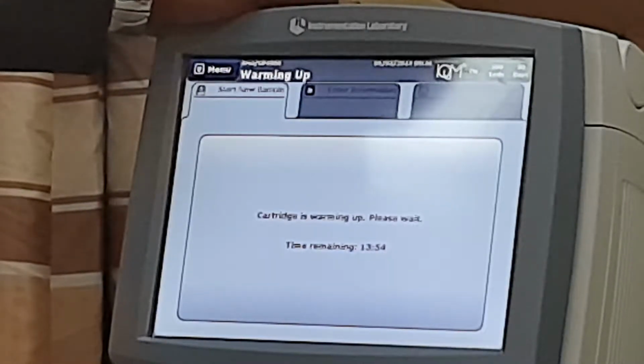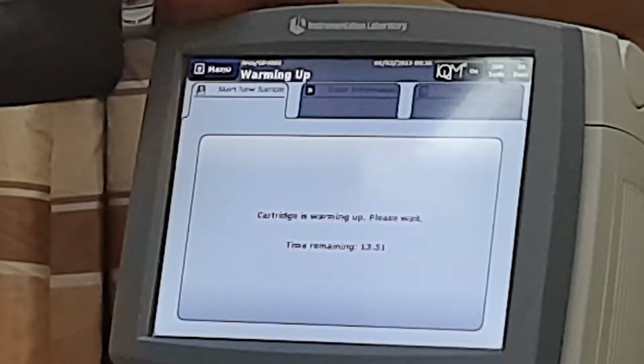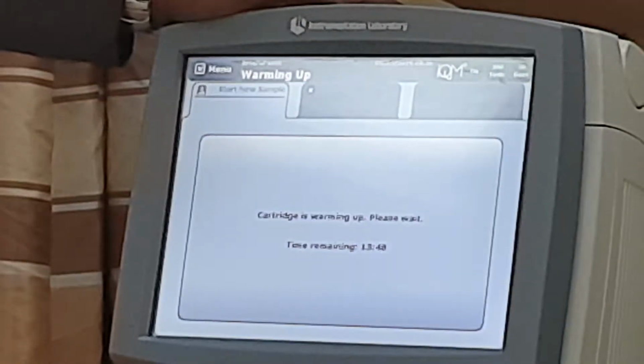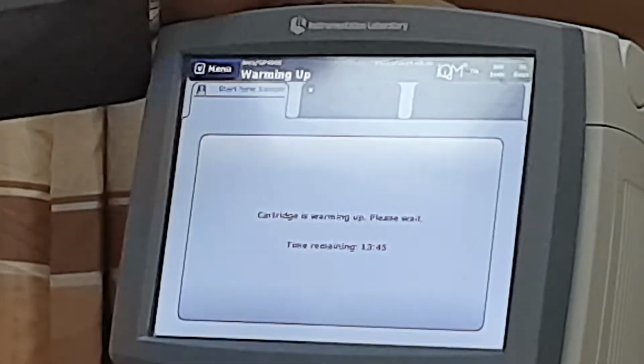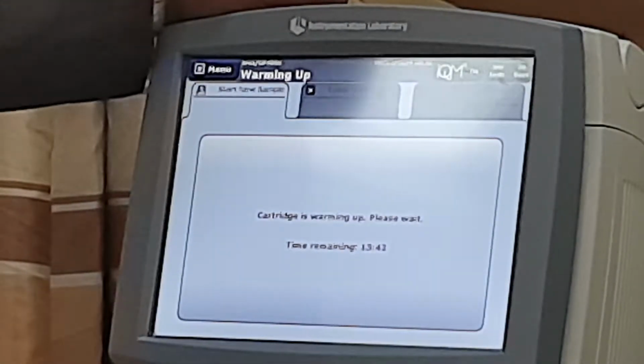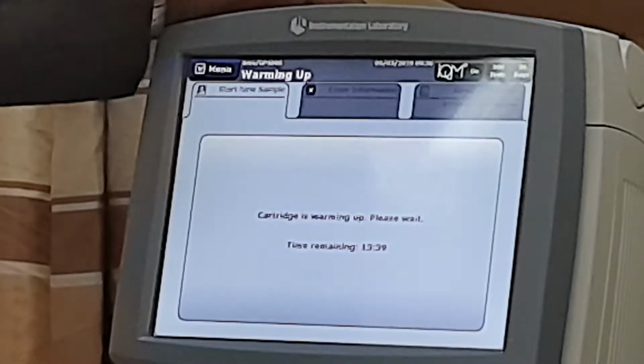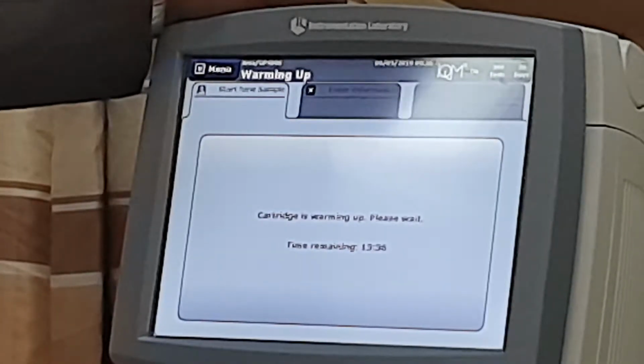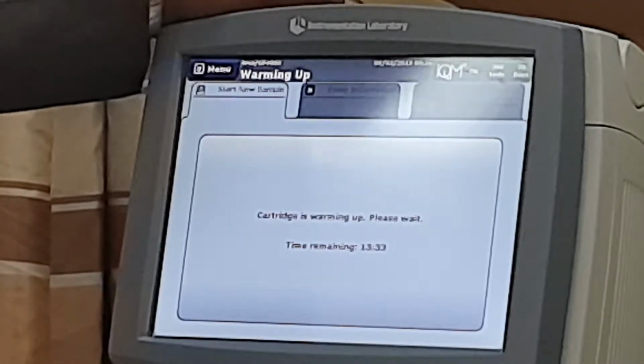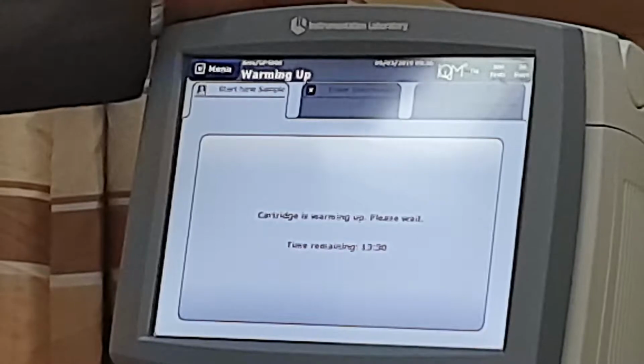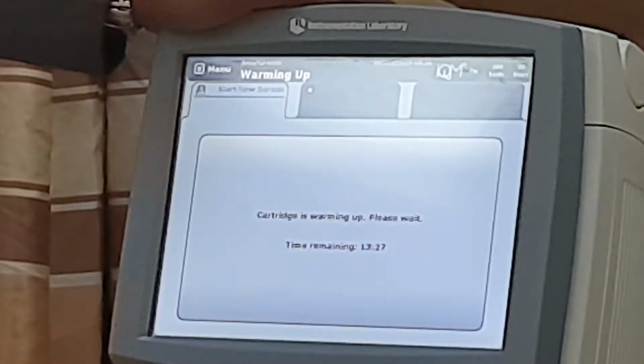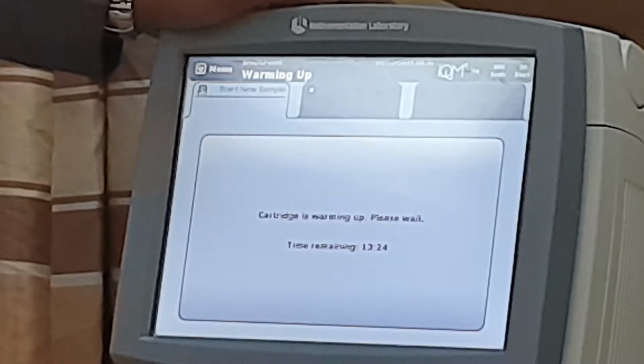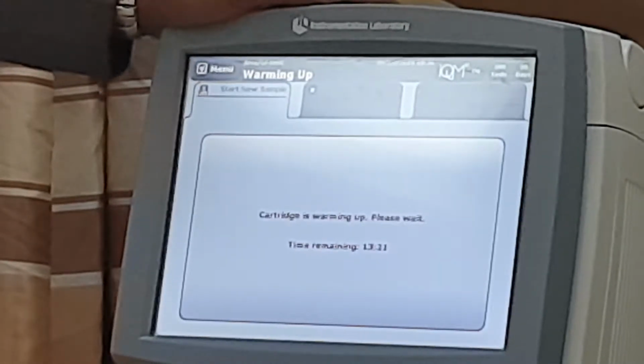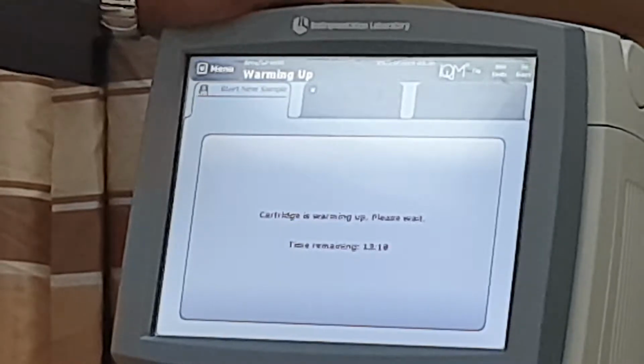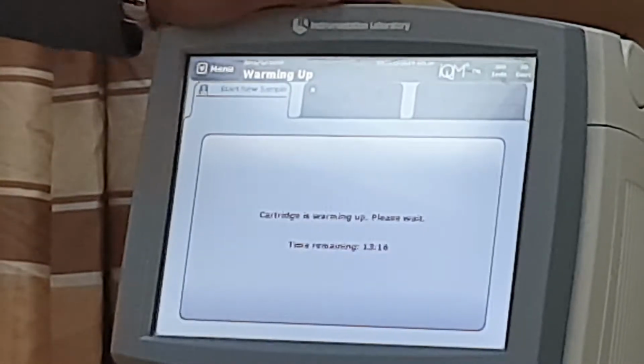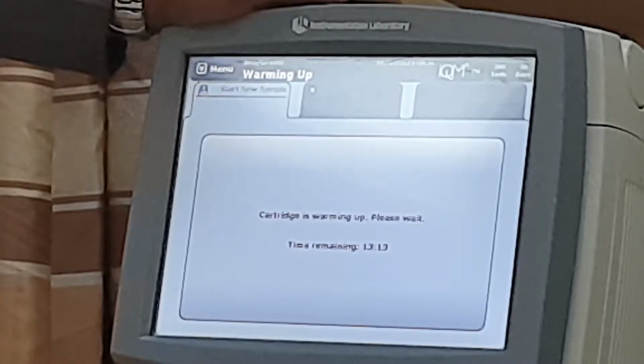We have a system inside that software. We will call it IQM. IQM means intelligent quality management. Why is it intelligent? Why is it a very smart system? Because the machine will run control for you automatically by 4 levels, and we will talk about those 4 levels also. After that, the machine will detect if there is any error with each level, with each parameter. The machine can make a corrective action or correct that parameter. It's not okay or a failed control.